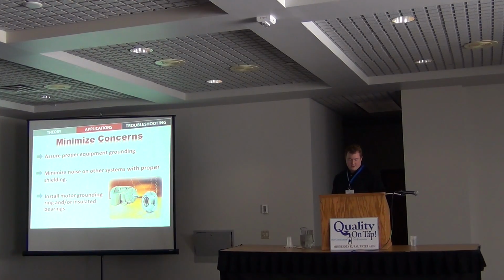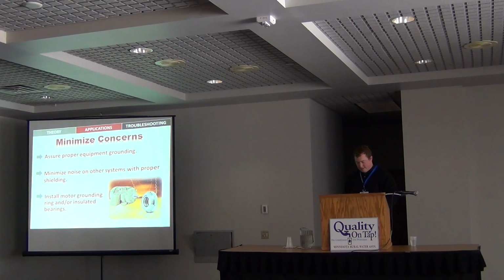VFD output conductors also should be either shielded cable or in rigid steel conduit that contains the noise produced on the cable from the output of the VFD. Don't run it in building wire in PVC conduit. That will greatly increase your chances of problems arising elsewhere on your control system, speaker system, whatever it might be. And that is most of the concerns.